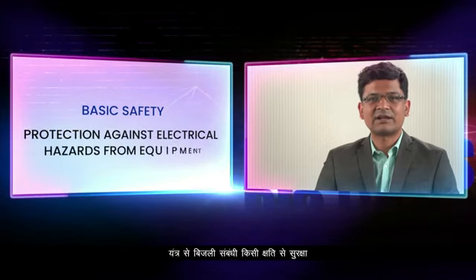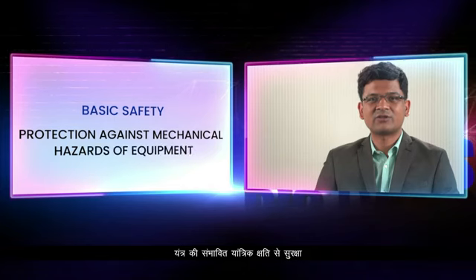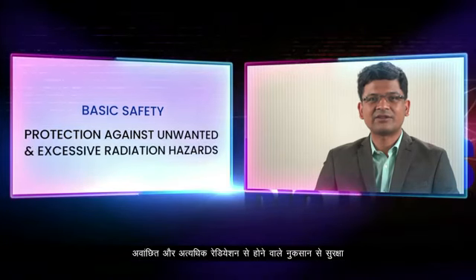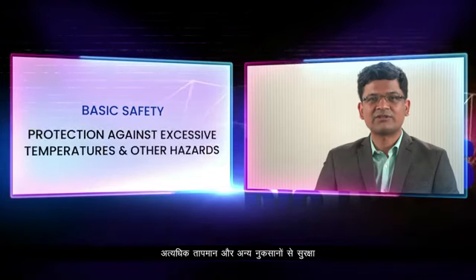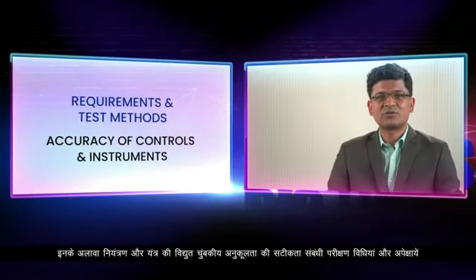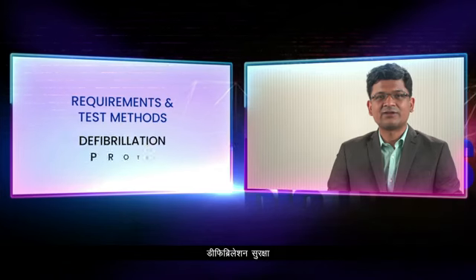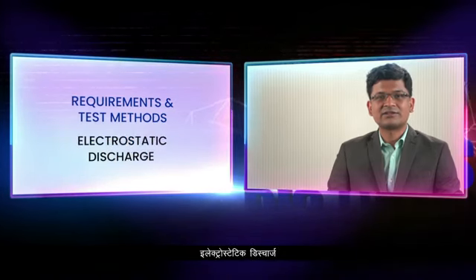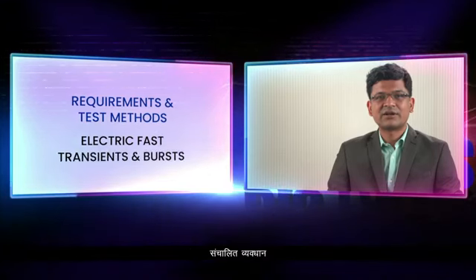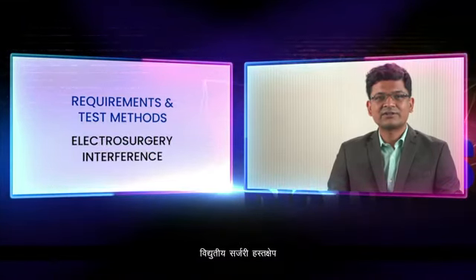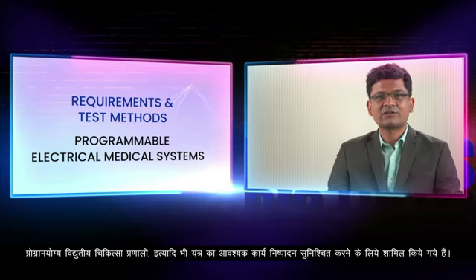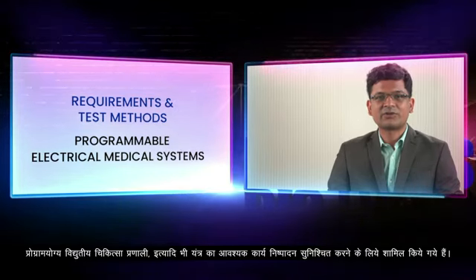For ensuring basic safety, this standard covers requirements and test methods for protection against electric shock, protection against electrical hazards from the equipment, protection against mechanical hazards of the equipment, protection against unwanted and excessive radiation hazards, protection against excessive temperatures and other hazards. In addition to this, requirements and test methods concerning accuracy of controls and instruments, electromagnetic compatibility, defibrillation protection, filters, electrostatic discharge, electric fast transients and bursts, conducted disturbances, electrosurgery interference, construction, alarm systems, programmable electrical medical systems, etc. are also included to ensure essential performance of the equipment.